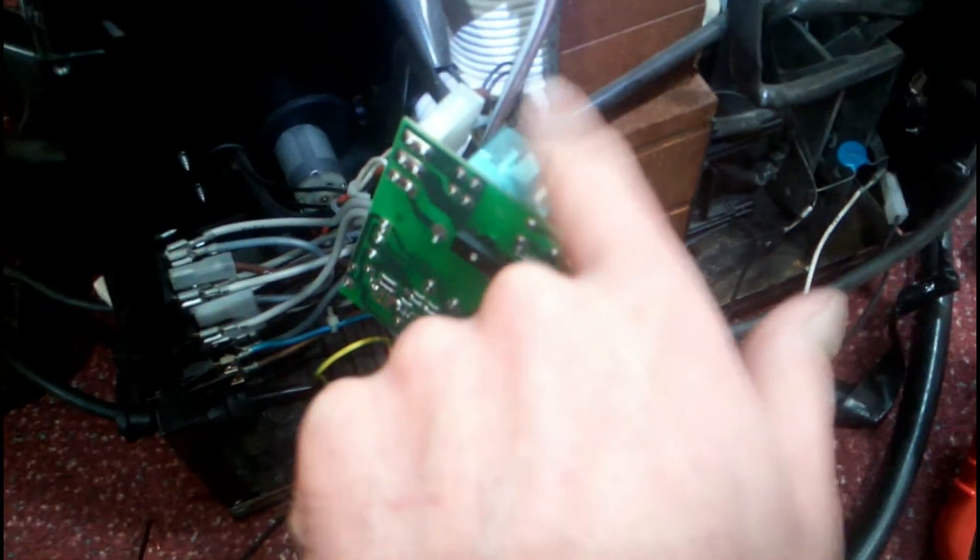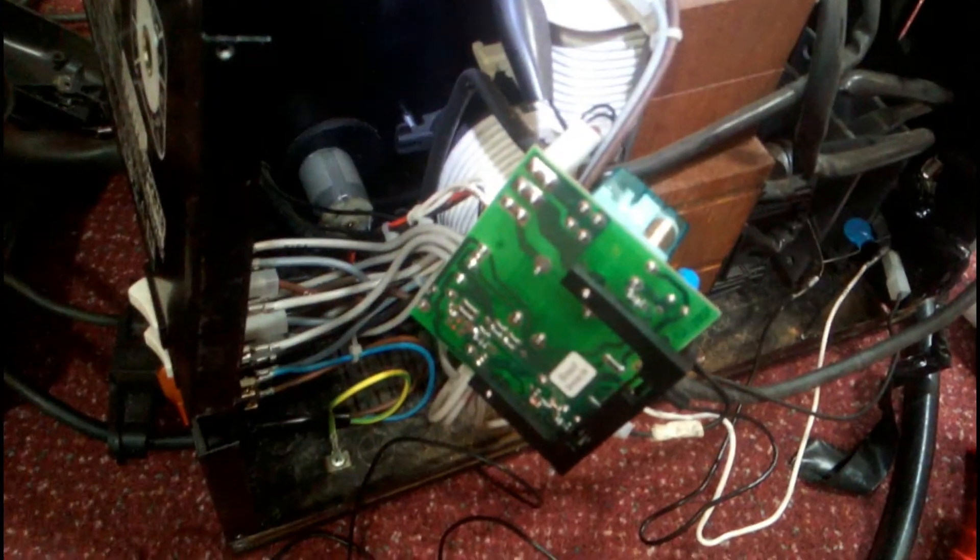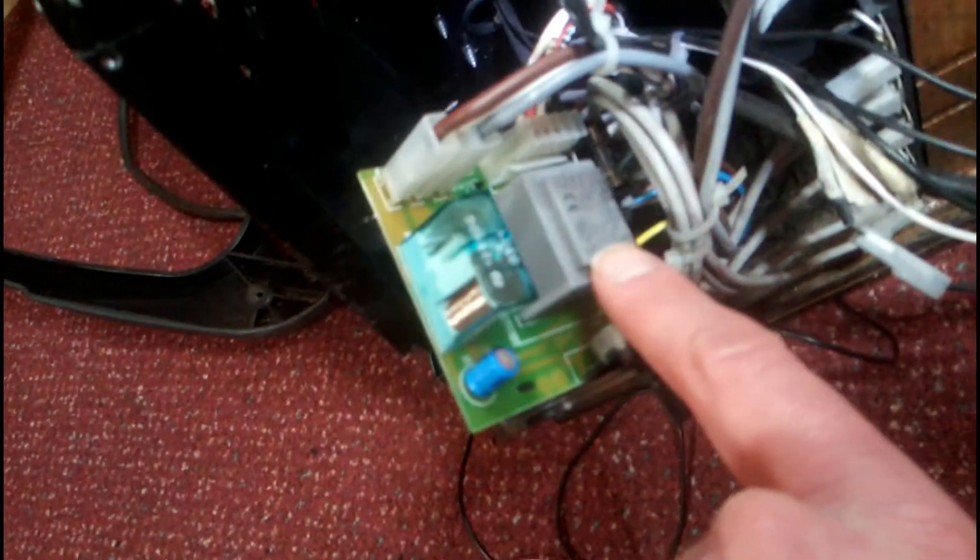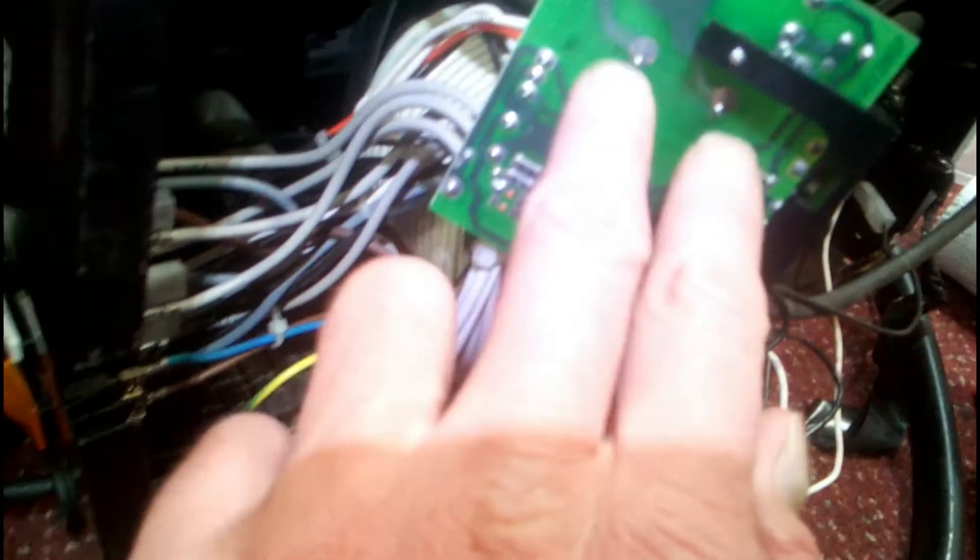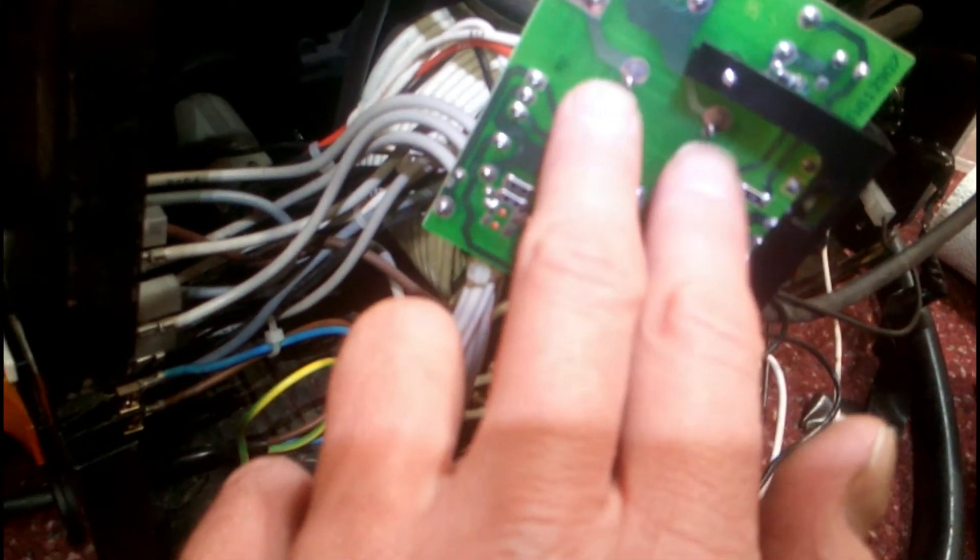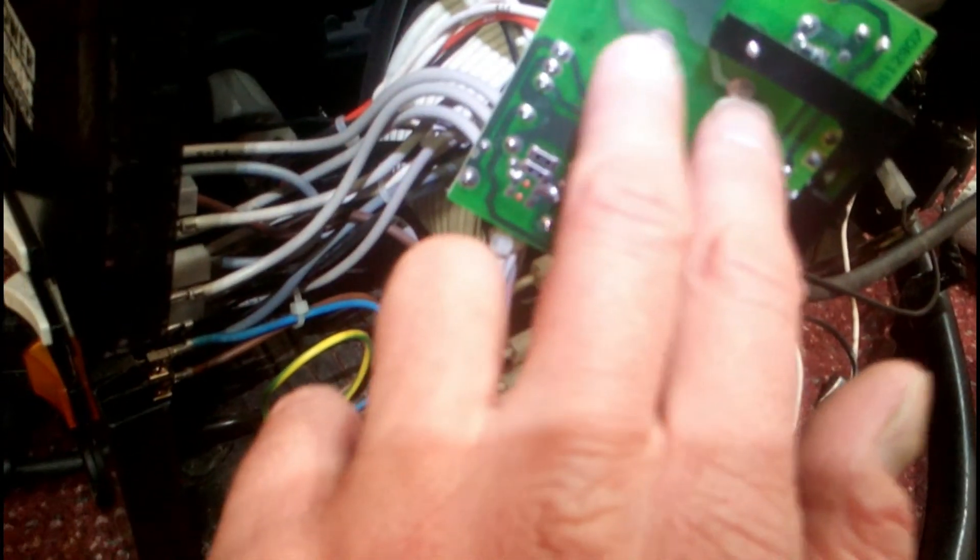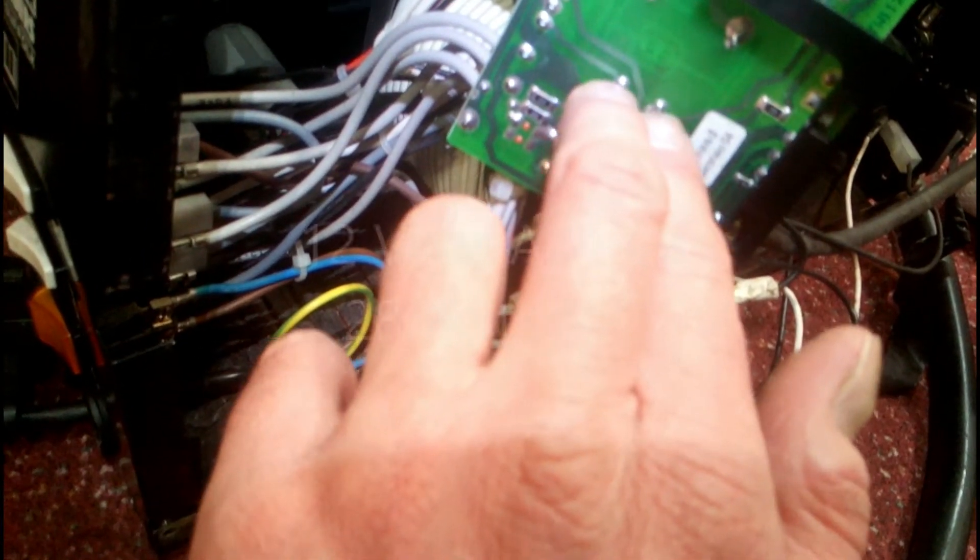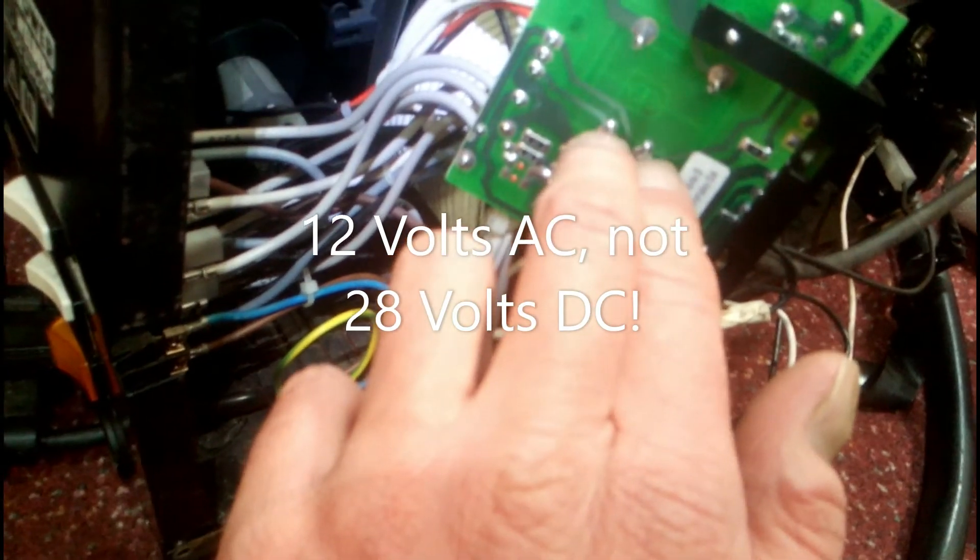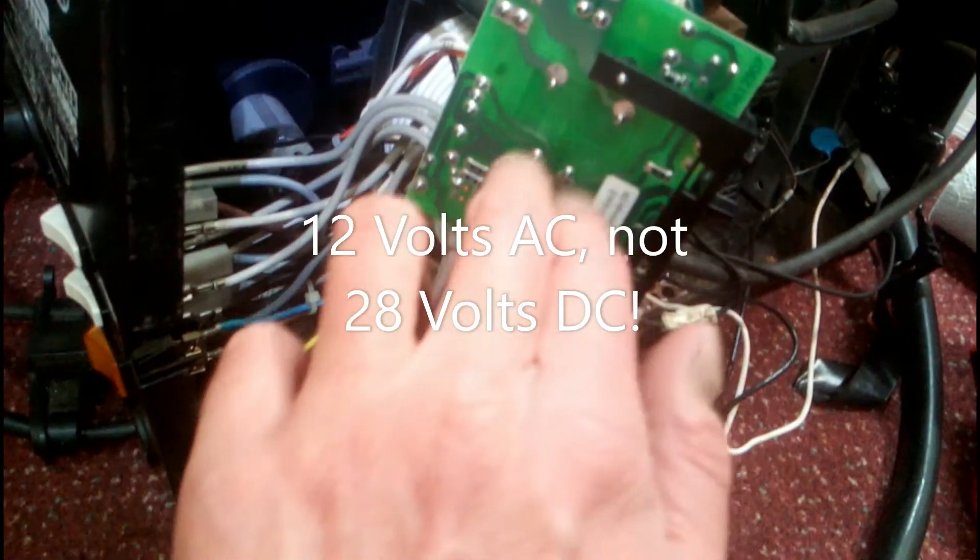So I know that this relay is good or should be good. What I've done is I've tie wrapped the trigger on the torch here so that the trigger is held in. What I want to do now is test this transformer is working. We should have 240 volts AC on these two pins of the transformer and we should be getting 28 volts DC at these two pins as it comes out of the transformer.